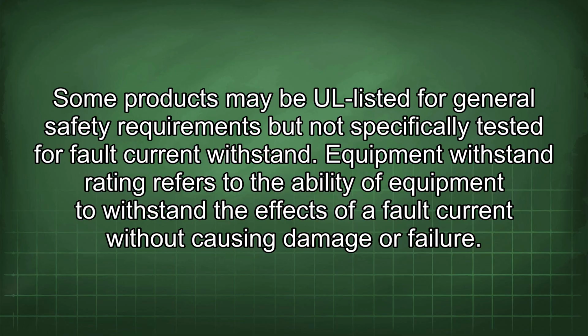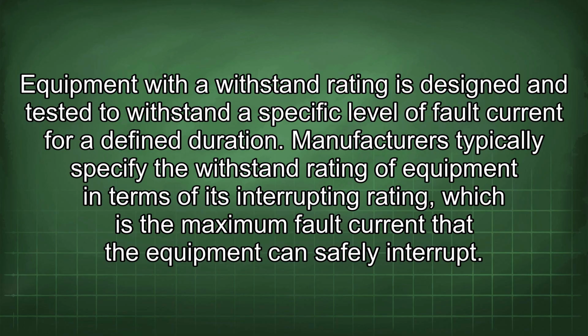Equipment withstand rating refers to the ability of equipment to withstand the effects of a fault current without causing damage or failure. Equipment with a withstand rating is designed and tested to withstand a specific level of fault current for a defined duration. Manufacturers typically specify the withstand rating of equipment in terms of its interrupting rating, which is the maximum fault current that the equipment can safely interrupt.